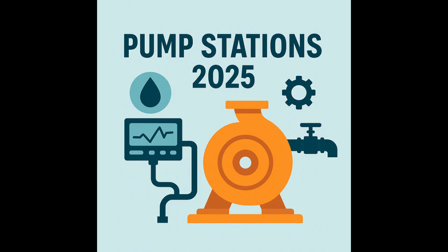Okay, so envelope, then pump selection. What's the third pillar? The third is absolutely critical: proper functional control. Because even with the perfect pump and a well-defined envelope, it won't matter if the controls run it poorly. Sure. This means implementing smart control strategies. Things like well-level controls that decide precisely when to start and stop pumps, maybe constant level controls to keep the downstream system stable, and definitely sophisticated pump sequencing and lead-lag control that intelligently shares the load among multiple pumps, preventing one from getting overworked. Okay. And modern controls now often add variable frequency drives, VFDs, or even predictive logic using AI for real-time fine-tuning of pump speed and operation. So this is kind of like the cruise control in your car analogy again. Intelligently adjusting power input to keep you smooth and efficient, instead of constantly flooring the gas, then slamming the brakes.